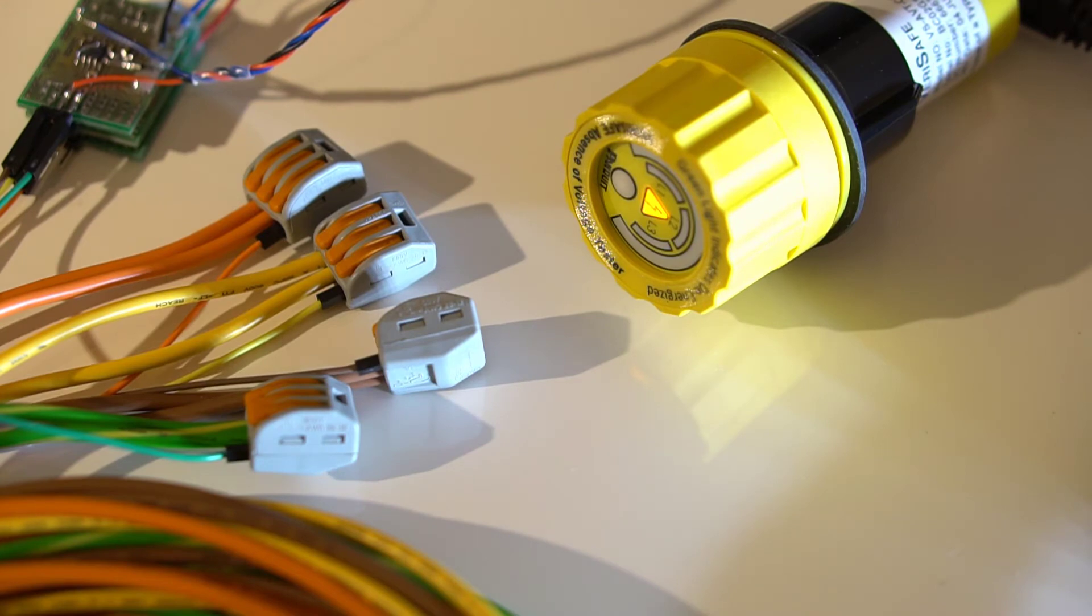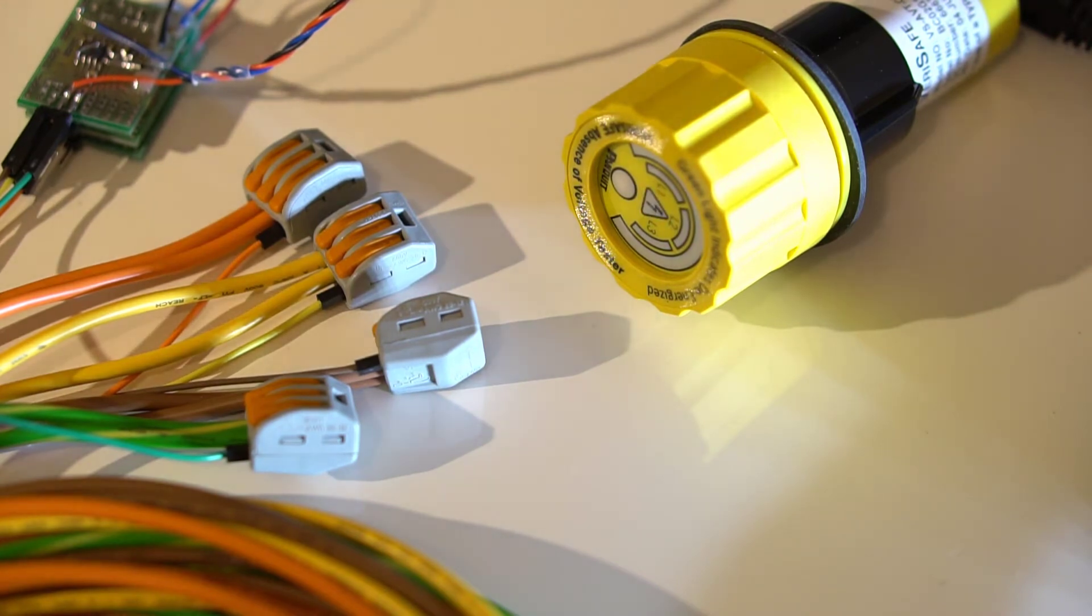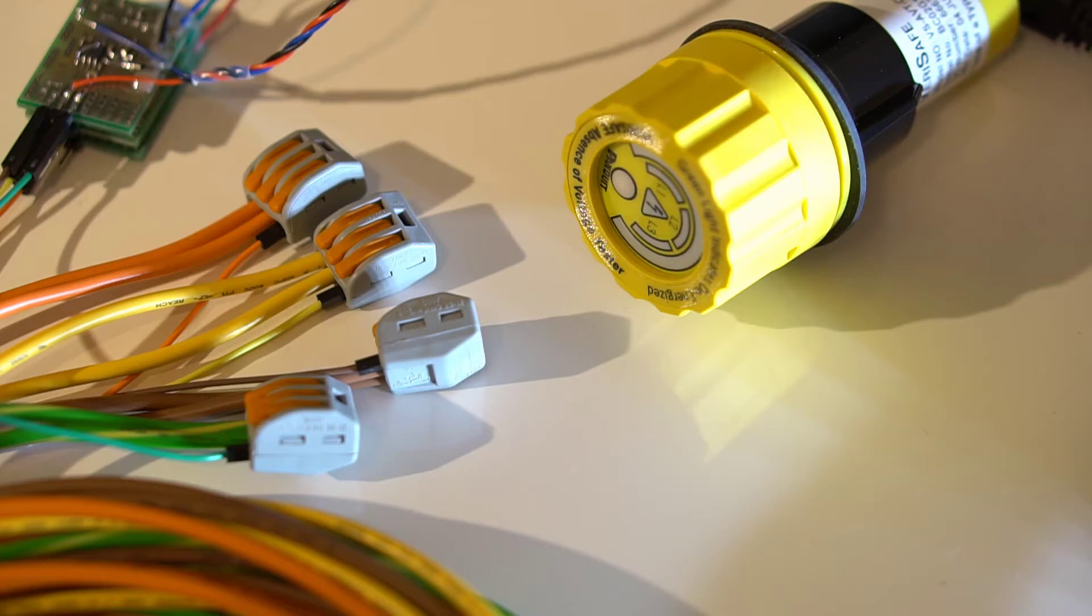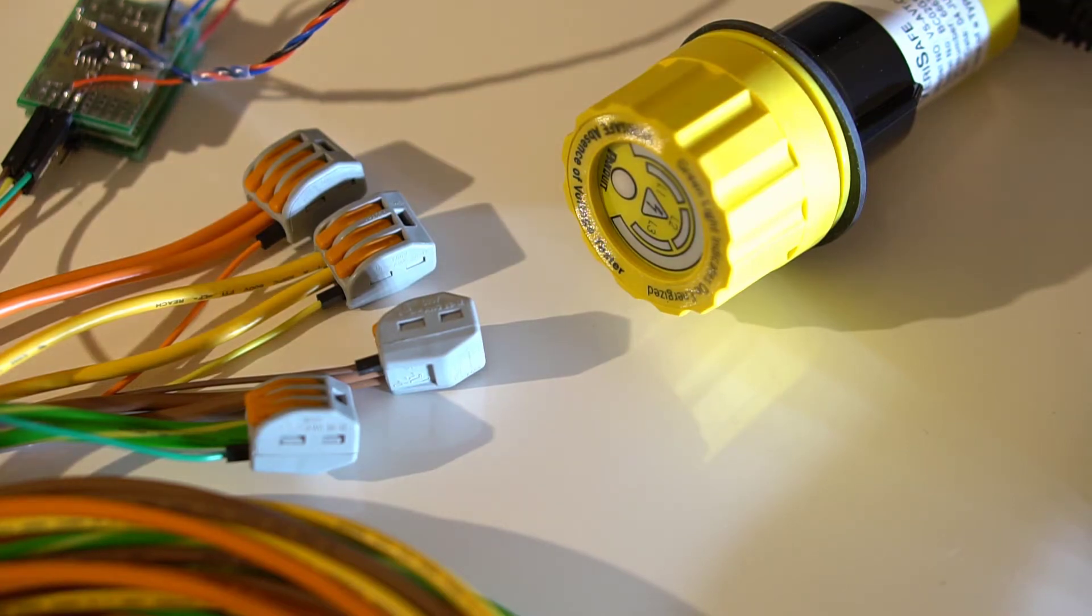And then I see two flashes, which are a code. The value two means that a voltage has been detected. Ordinarily, three red bars should also be lit, one per phase, in order to indicate that there is a hazardous voltage. But the three-phase simulator doesn't generate a hazardous level, but it is sufficient to allow the VeriSafe tool to still identify that a voltage is present, and that therefore the system is still energized and should not be worked on.